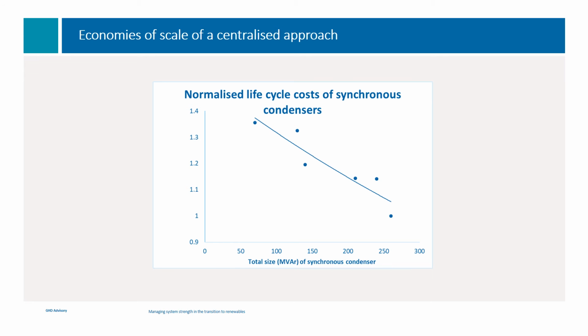As the plot shows here, there's a significant economy of scale arising from selecting larger units than, for example, installing multiple smaller units. This is all based on a total of 400 MVA of provision, either 8 times 50 MVA units through to ultimately 400 MVA units. There's roughly a 40% to 50% increase in life cycle costs going for multiple smaller units as opposed to single units or a select few strategically placed medium-sized units.